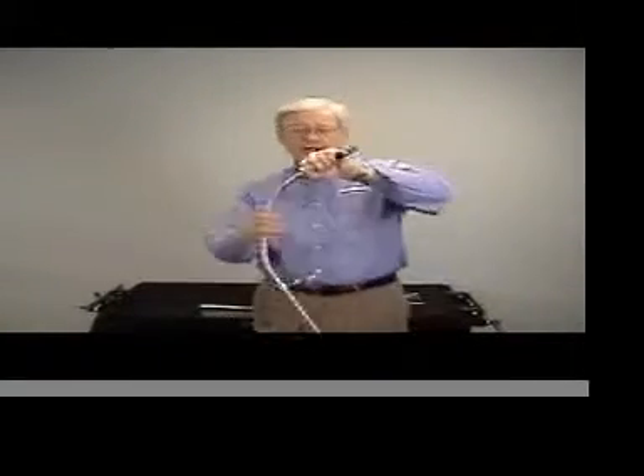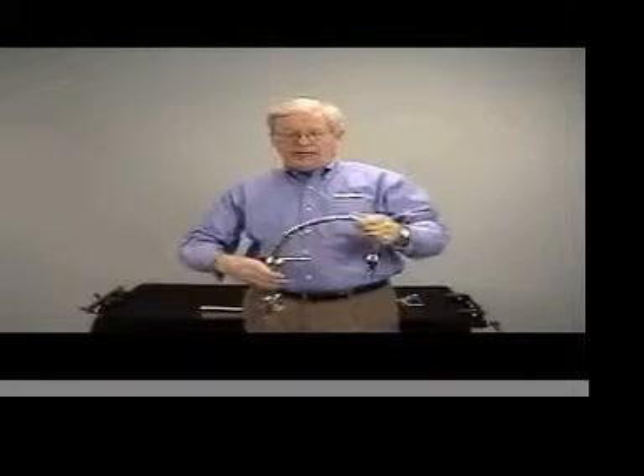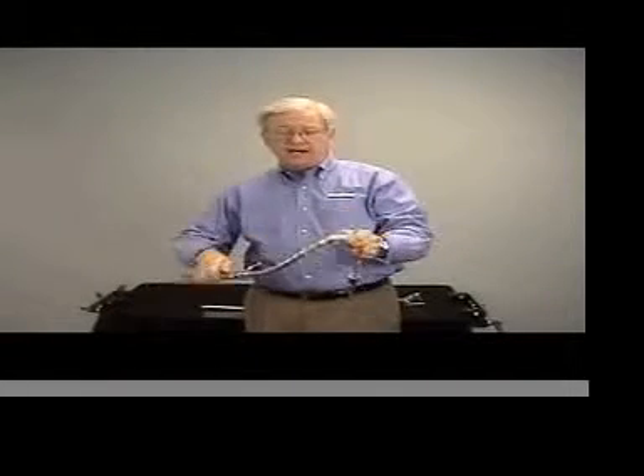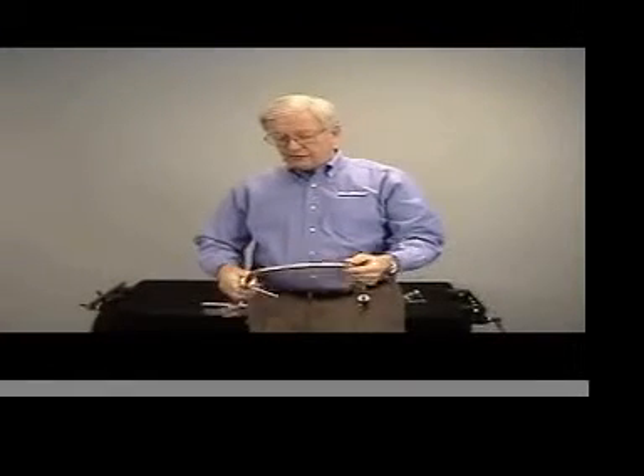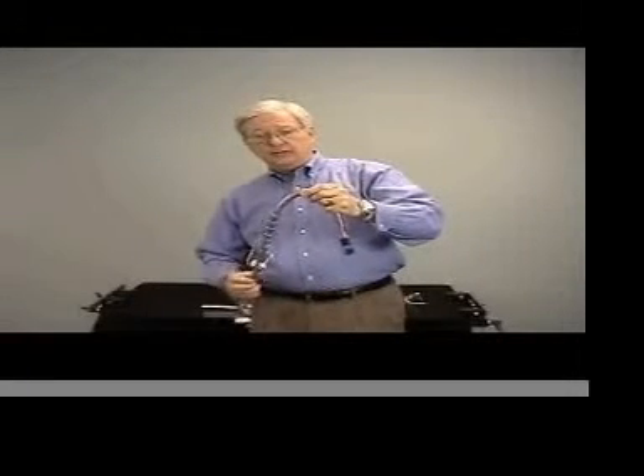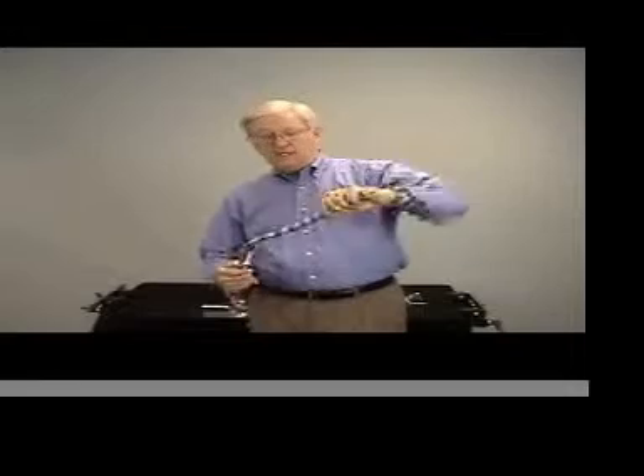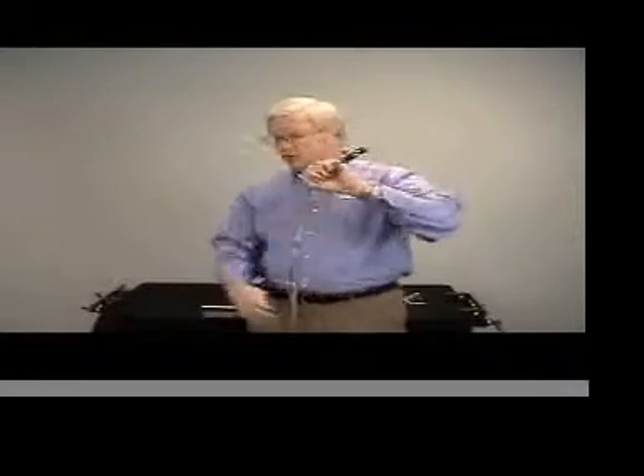The one-piece arm right now, it's pre-tensioned. I would be able to open this by spinning the entire housing counterclockwise. And now I have the space that's necessary for cleaning and sterilization. When it comes back to the operating room, make sure that the tensioning knob is all the way counterclockwise, and then spin in a clockwise manner until you meet resistance, and the arm is now pre-tensioned.